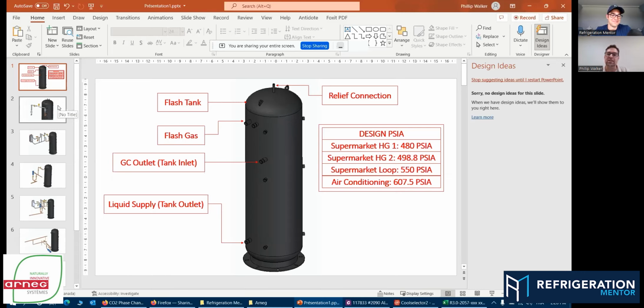So we're doing a lot of indoor air handling units with CO2 coils, coming right off the rack, direct expansion. This isn't glycol, it's 100% CO2, and it's going very well. The good thing is that mixed-use buildings we're also limited in where we can put our gas cooler, and CO2 helps us overcome some of those hurdles and obstacles. We're up to 12 stories right now where we're installing dry gas coolers. They put dry pavilions out and fence off the gas cooler, and we're running piping 120 to 130 feet on the vertical run. We're putting P-traps in there for oil, and this is working.